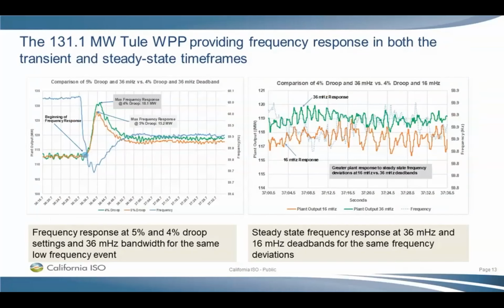This last slide I wanted to show you is that wind can produce frequency control in the transient time frame and then in a normal steady state time frame. You can change certain things at the wind plant, like the droop setting and the deadband, pretty easily. The one on the left shows the response at 5% droop and a 36 millihertz deadband. The one on the right is 4% droop at a 16 millihertz deadband. You can see you get more response in normal steady state operation with a 16 millihertz deadband and a 4% droop.